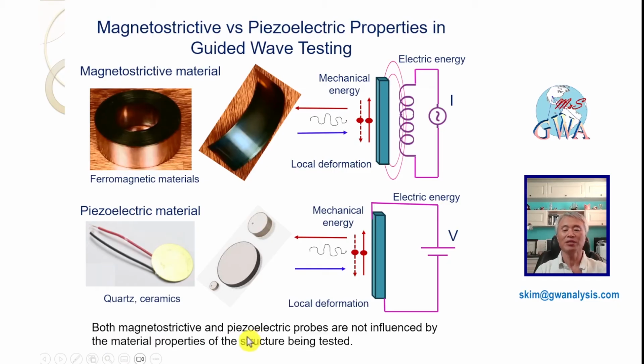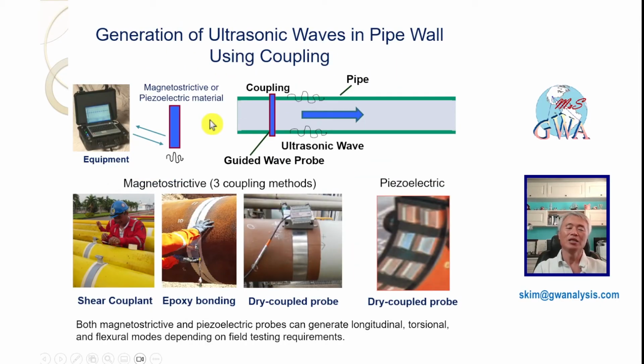Both magnetostrictive and piezoelectric probes are not influenced by the material property of the structure being tested because the waves are generated indirectly. This slide shows a schematic drawing of generation of ultrasonic waves in the pipe wall using couplings. For transmitting guide waves on pipelines, we use three couplings: shear couplant, epoxy bonding, and dry coupled probes. By changing the probe alignment, spacing, and coverage of pipe circumference, both magnetostrictive and piezoelectric probes can generate longitudinal, torsional, and flexural modes depending on the field testing requirements.